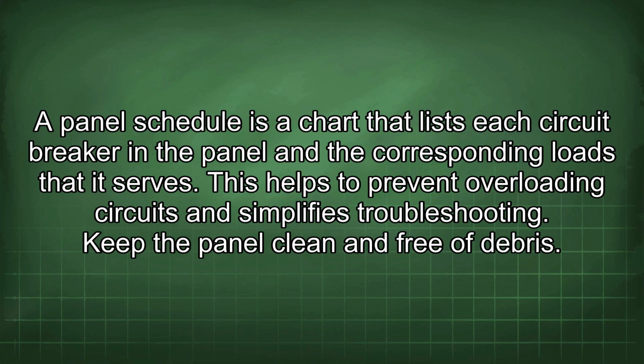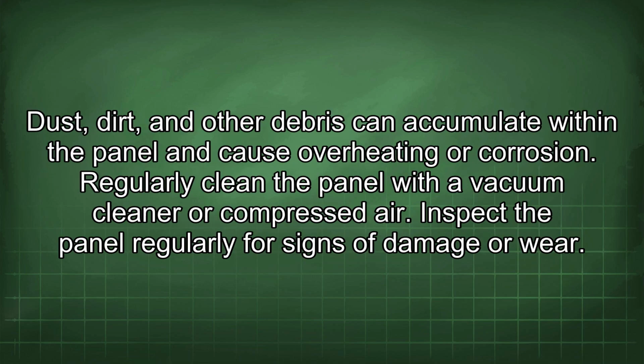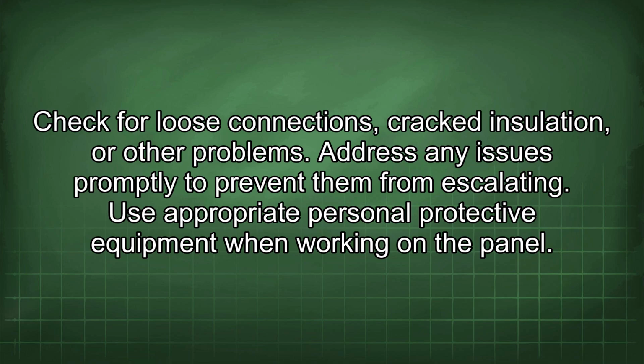Keep the panel clean and free of debris. Dust, dirt, and other debris can accumulate within the panel and cause overheating or corrosion. Regularly clean the panel with a vacuum cleaner or compressed air. Inspect the panel regularly for signs of damage or wear. Check for loose connections, cracked insulation, or other problems. Address any issues promptly to prevent them from escalating.